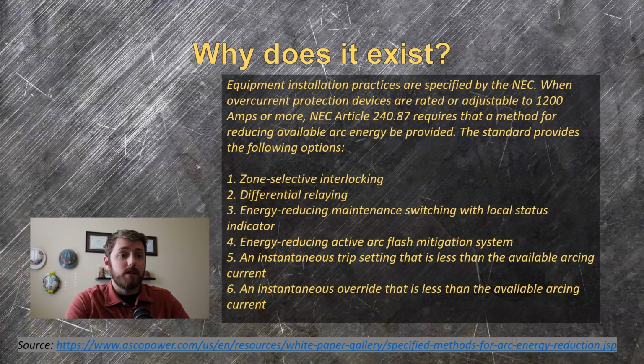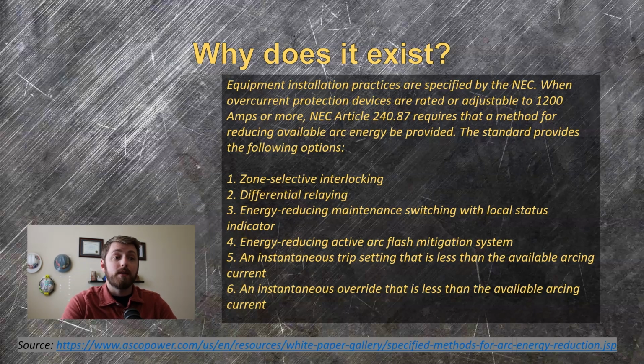This rule only applies to residential and commercial. Utility and industrial applications don't have to worry about meeting the NEC 240.87 requirement. However, maintenance mode and some of these other methods can make it a lot easier to stay in compliance with other OSHA or NFPA requirements.